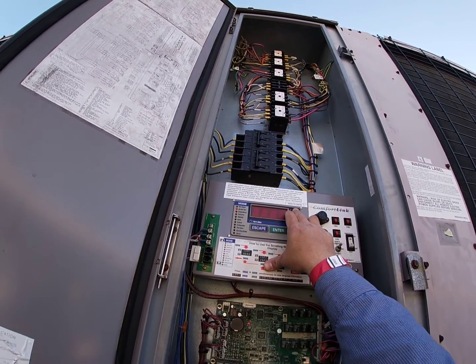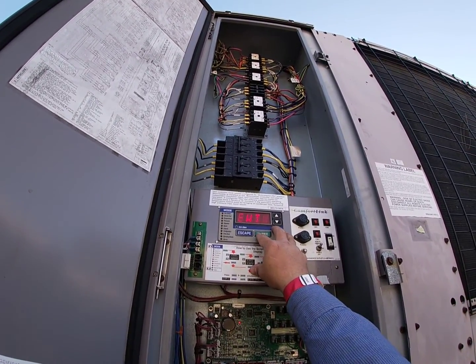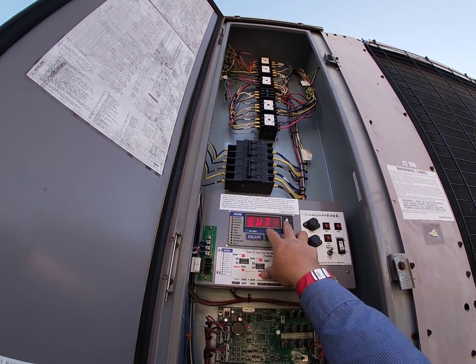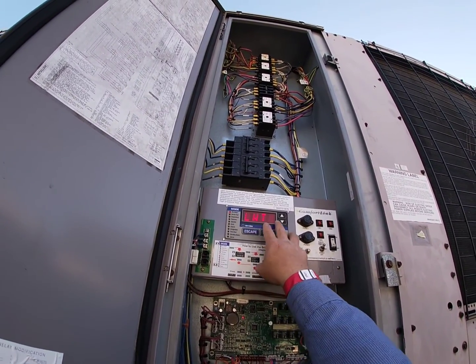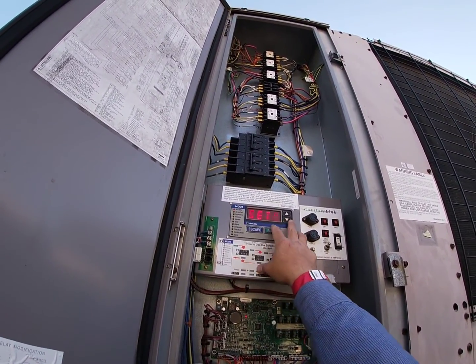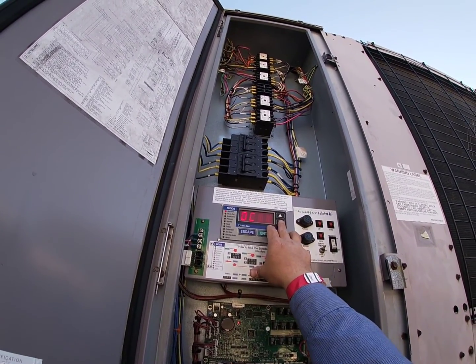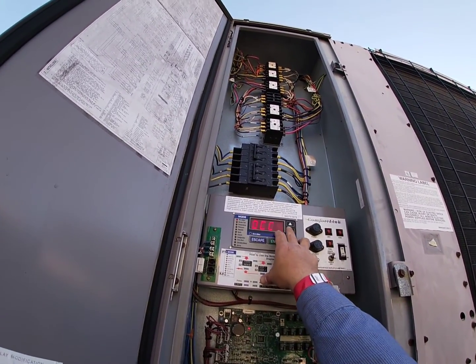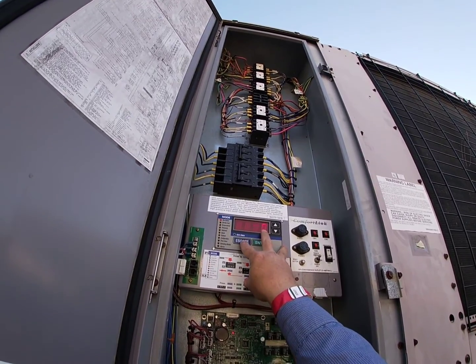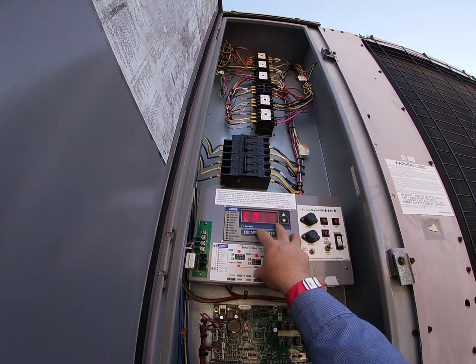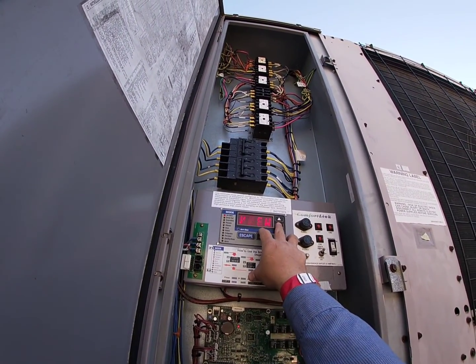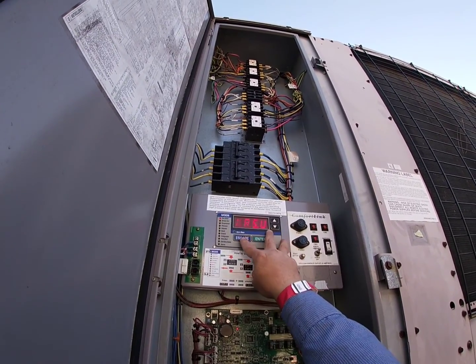Now let's look at run status. View - entering water is 54, leaving water is 57, your set point's 44. Occupied, yes, so it should possibly kick on unless there's anything else holding it back, which I don't think so. Run.